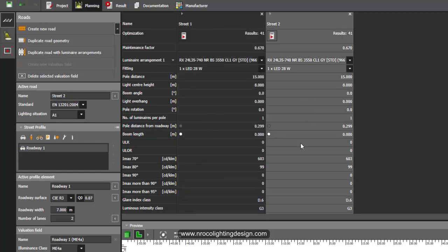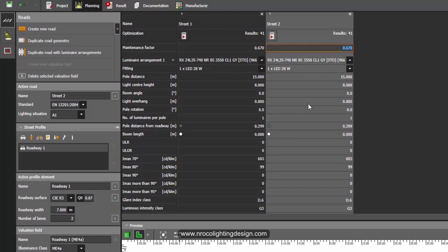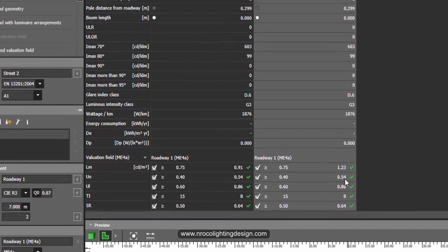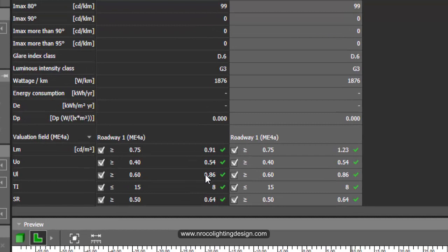What I'm going to do is I will just change this maintenance factor as 0.91 and let's see the value. By this one you can easily see that once you change the maintenance factor into higher value, the lumen output and all the values on the report will become better.